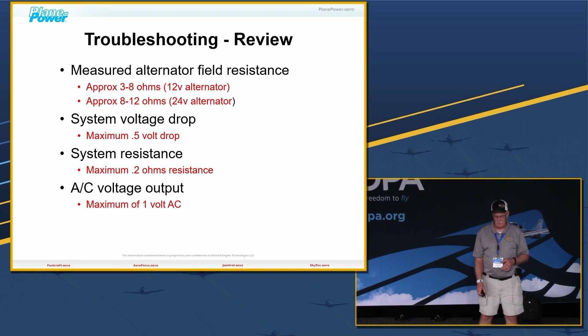These are just some troubleshooting numbers. They're okay if you know what you're looking at, but the ohms themselves don't have to be these exact numbers when you're doing a field check. It basically has to do with how much resistance is in that circuit, that's all you're trying to figure out. Think about it: you've got brushes that go against the slip ring. If the brush wears out, the spring tension decreases. Less pushing on the slip ring means it might bounce a little, and the system sees it as a flutter or kicks the system out because it sees a fault.